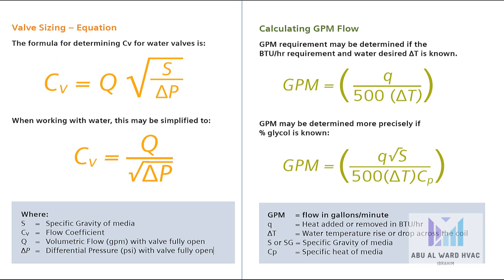For water specifically, Cv equals Q divided by the square root of ΔP, where S is the specific gravity of the media, Cv is the flow coefficient, Q is the volumetric flow rate in GPM with valve fully open, and ΔP is the differential pressure in PSI with the valve fully open.